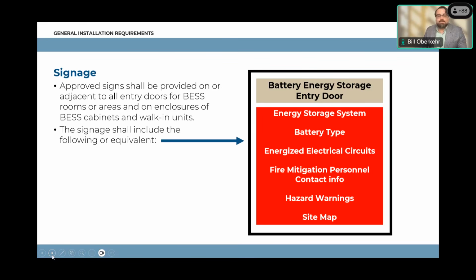In addition, we need signage that identifies the system as an energy storage system, what type of battery, and standard NEC, National Electric Code signage requirements, like indicating there are energized electrical circuits. Critically, we need the contact information for hazard support personnel or fire mitigation personnel -- those subject matter experts who come to the site and assist the fire department -- to be on the signage outside the fence. We're looking at our peer review team to make sure that's the case within NYSERDA, and it's also critical that code officials check that before issuing a permit.